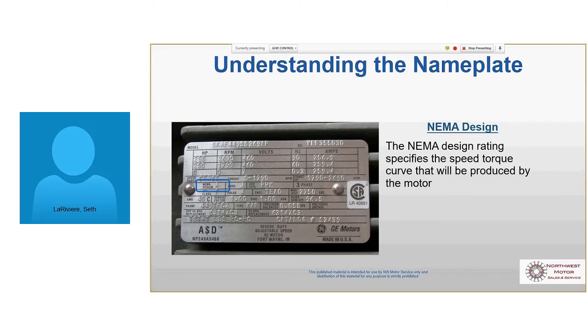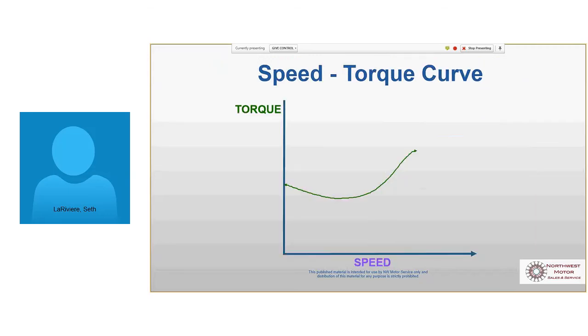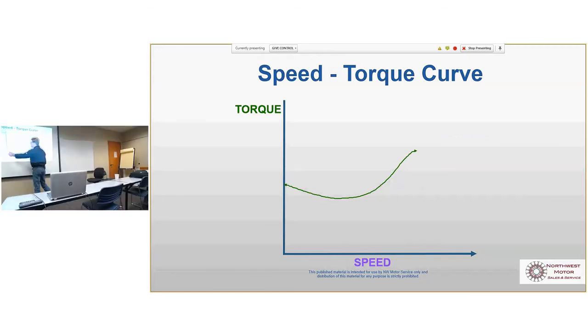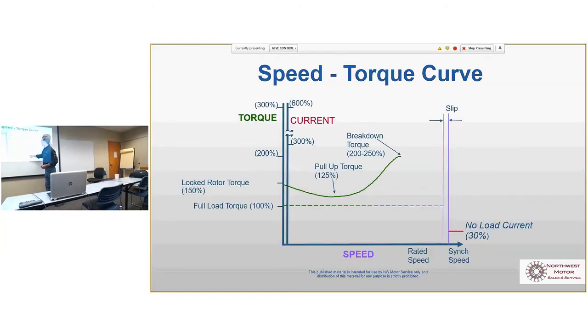NEMA Design A is the inrush profile of the amps that it draws when it's starting. KVA code letter, same, or NEMA Design A, I'm sorry, is torque. That's KVA code letter. And we talk about A, B, and C and why that might matter to these guys? Yeah, there's a slide here. So this is your basic speed torque curve. So here we are at 0 speed, and this is 1800. So when we start our motor, we have to produce the amount of torque to break it away, then it drops down a little bit, then it gets to the most torque it can produce. Below that, it would drop off and go to 0 speed.